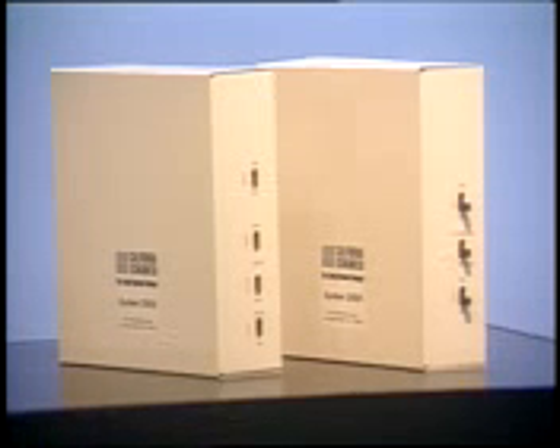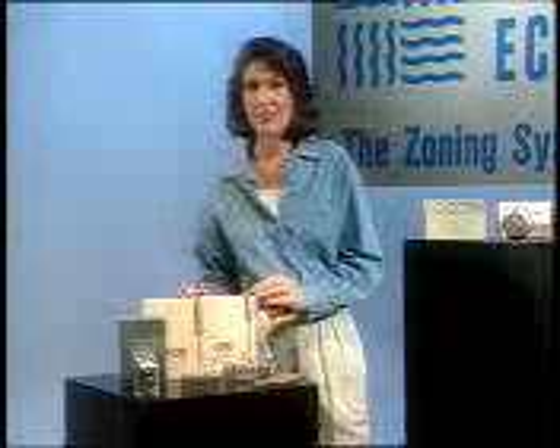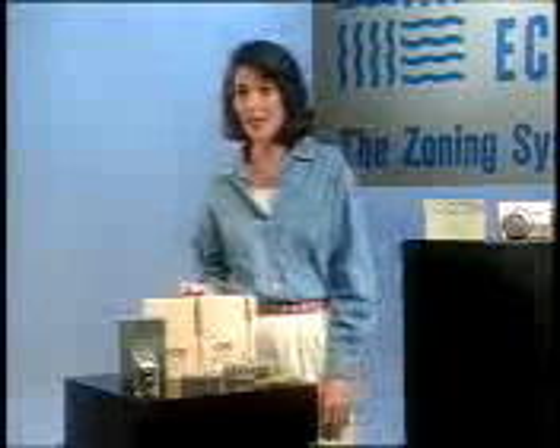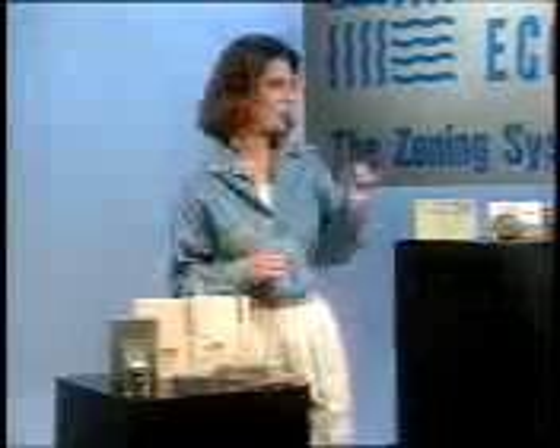The System 2000 controller is available in both auto changeover and manual configurations. The controller operates 1 heating and air conditioning unit and up to 20 thermostatically controlled zones. A room thermostat senses the temperature in each zone. These room stats can be mixed. They can be manual, programmable, or automatic.